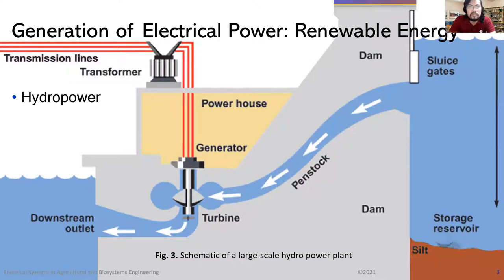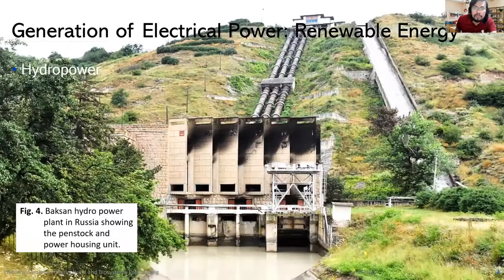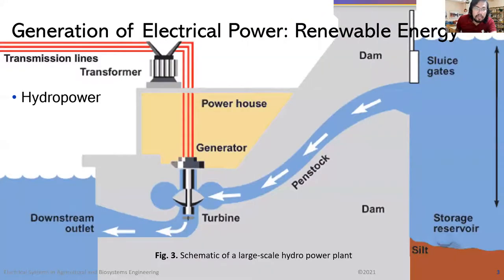Let's go to the operation of a hydropower plant. We have here a cross-sectional schematic of a plant — this is figure three. To the right is the water reservoir, usually at the upper location of a stream network where water is collected. This is the importance of damming rivers: we store the water, and it is released by gates — the sluice gate. The water enters the penstock, at the bottom of which is the turbine to receive the water going down via gravity, so the water flows with a fixed mass flow rate.